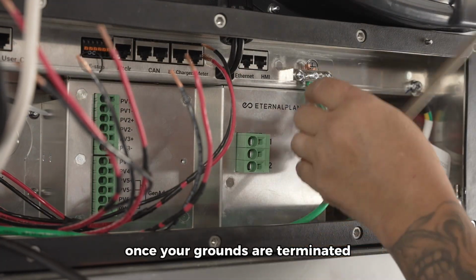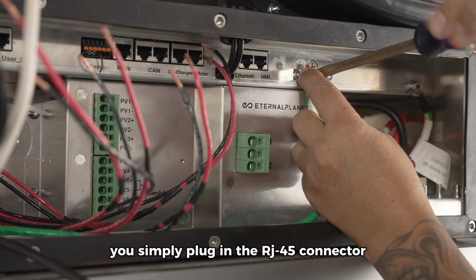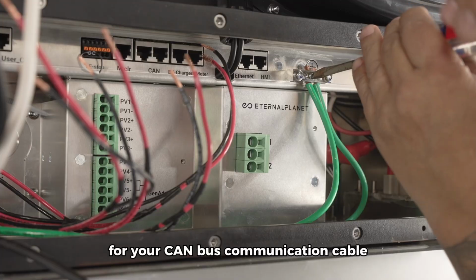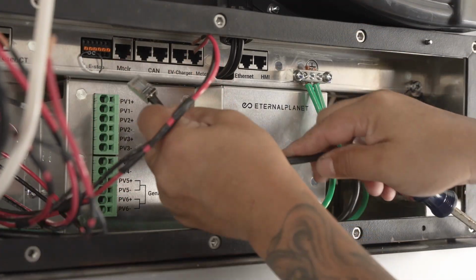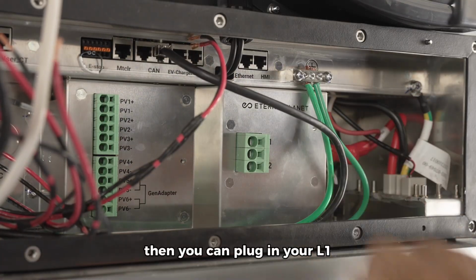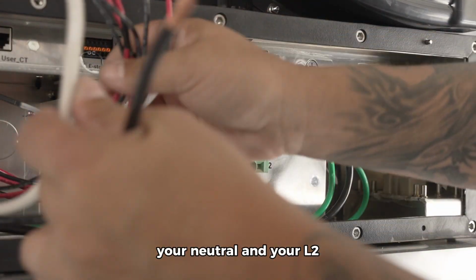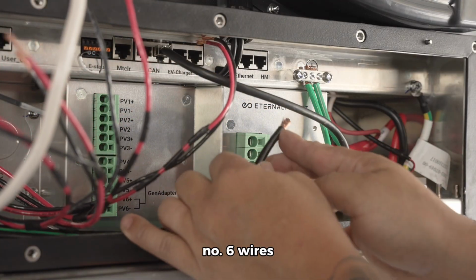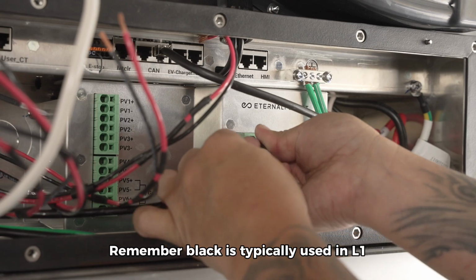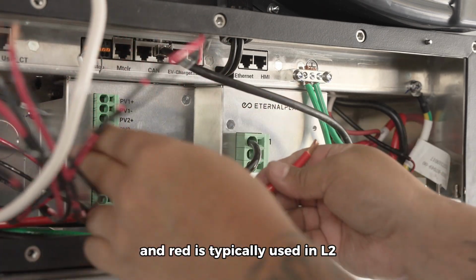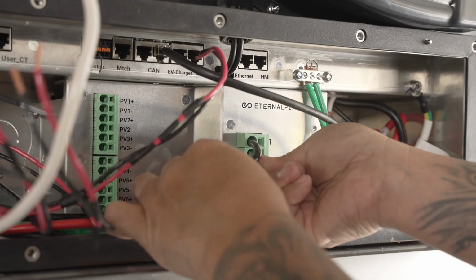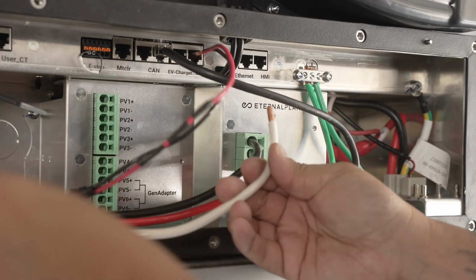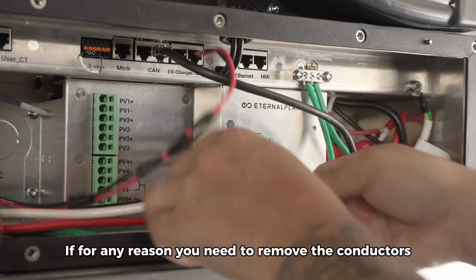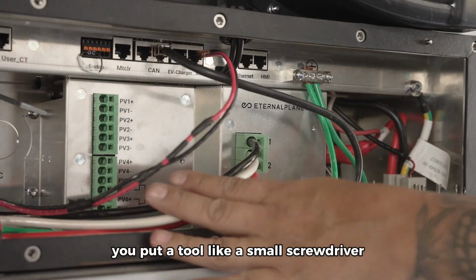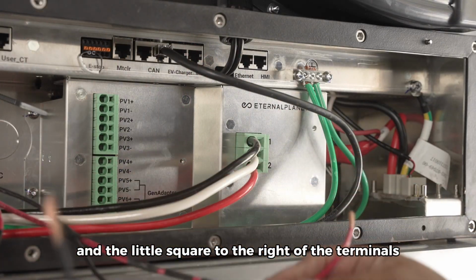Once your grounds are terminated, you simply plug in the RJ45 connector for your CAN bus communication cable. Then you can plug in your L1, your neutral, and your L2 number 6 wires. Remember, black is typically used in L1 and red is typically used in L2. If for any reason you need to remove the conductors, you put a tool, like a small screwdriver, in the little square to the right of the terminals and push in, and that will release the tab that holds the conductors in.